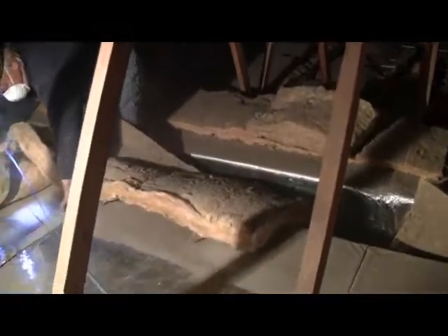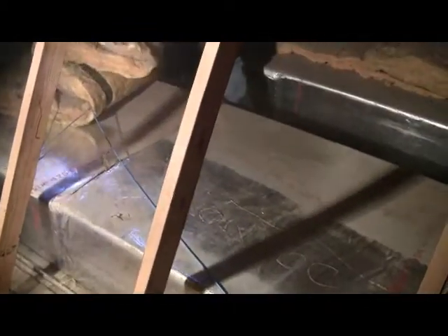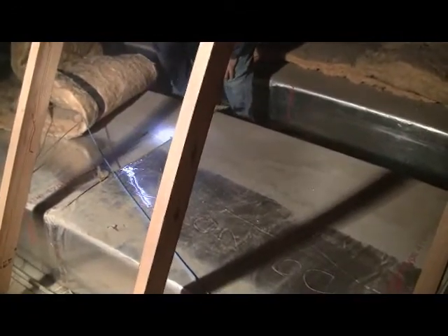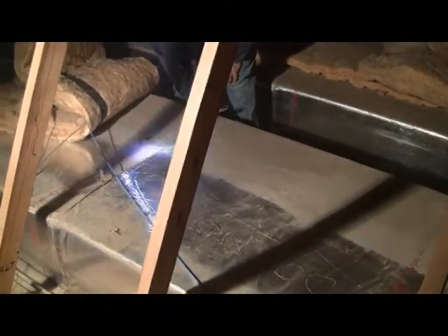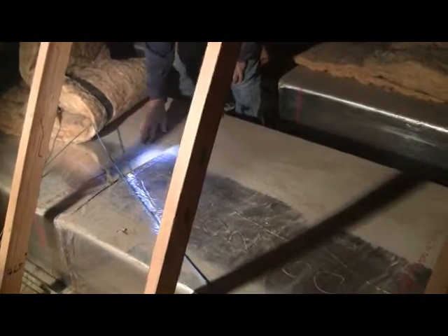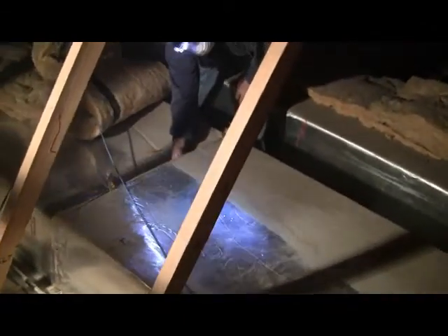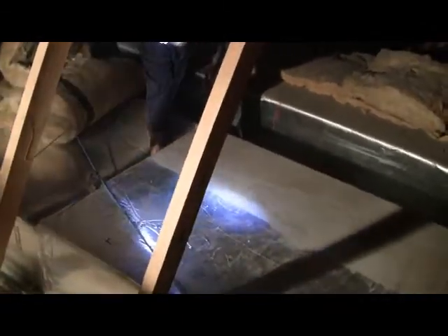See how this joint in the ducting system has come loose? I'm pulling this fiberglass back that's really doing very little good, but over time, this was held together with this metallic tape. Perhaps somebody tried to crawl across here or something, but I can actually reach inside the ducting system right here. I've got a major, substantial leak in this system.